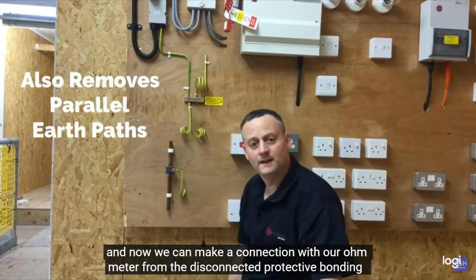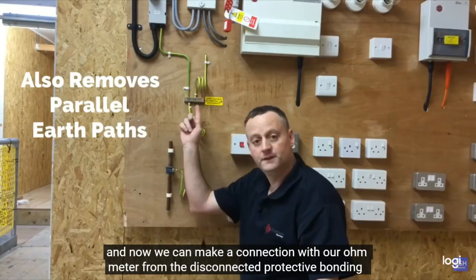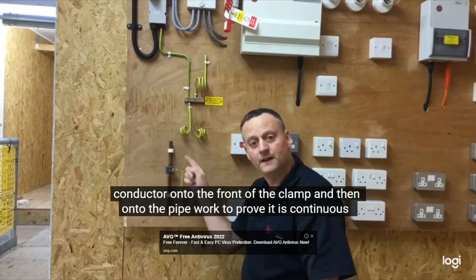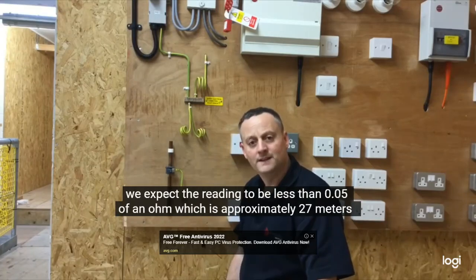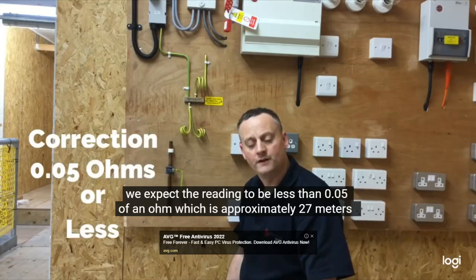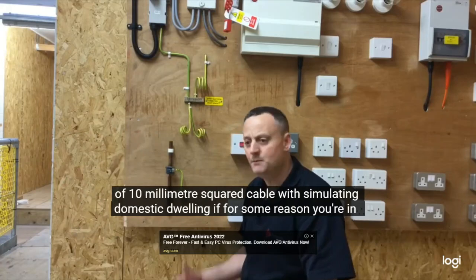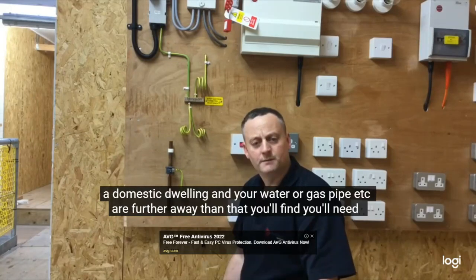And now we can make a connection with our ohmmeter from the disconnected protective bonding conductor onto the front of the clamp and then onto the pipework to prove it is continuous. We expect the reading to be less than 0.05 of an ohm, which is approximately 27 meters of 10 millimetre squared cable. We're simulating a domestic dwelling. If for some reason you're in a domestic dwelling and your water or gas pipe, etc., are further away than that, you'll need to increase the size to 16 millimetres squared.